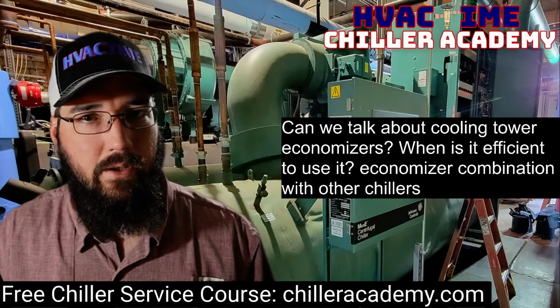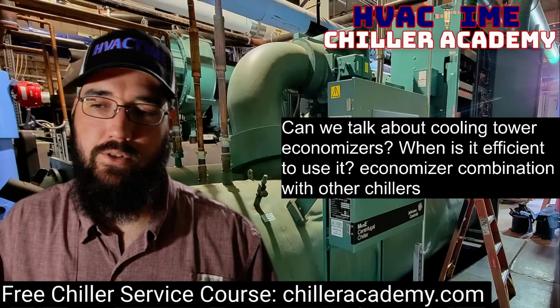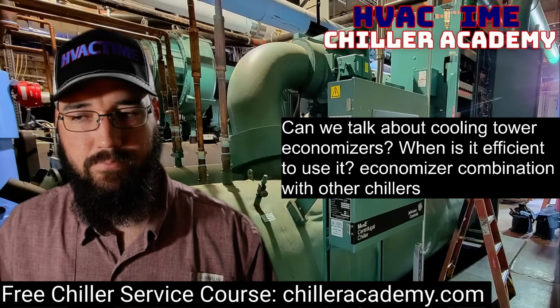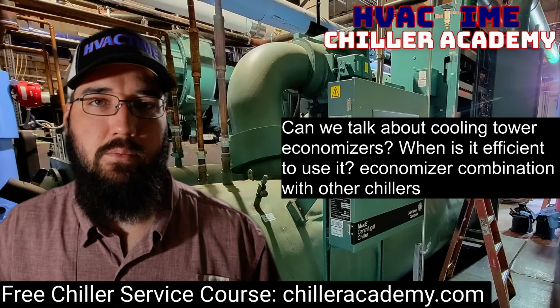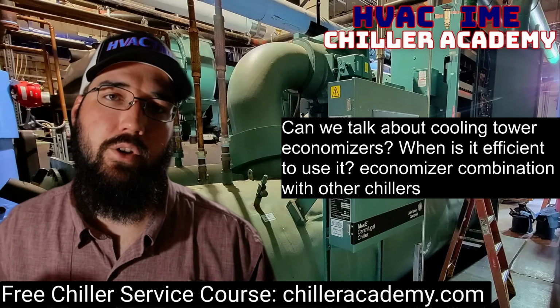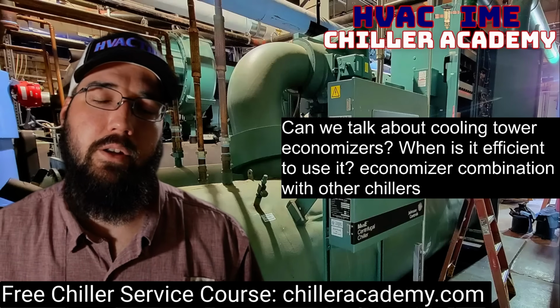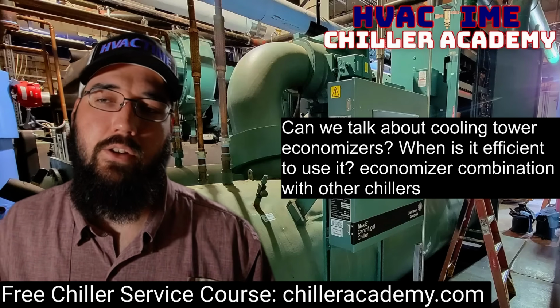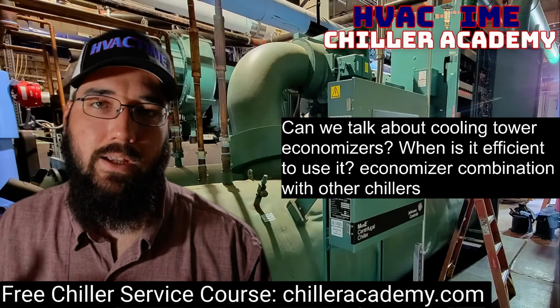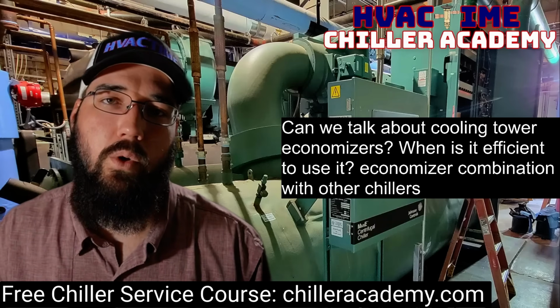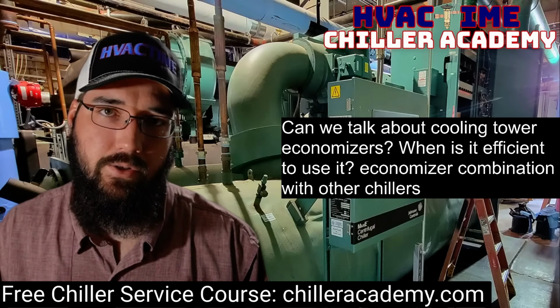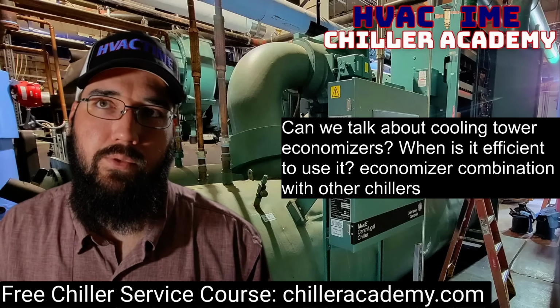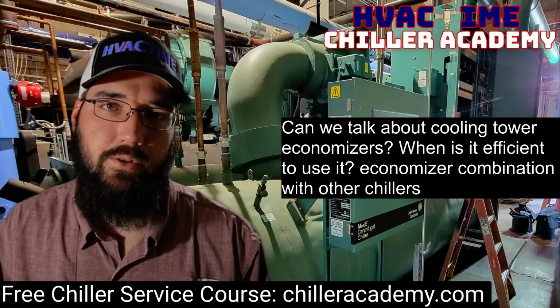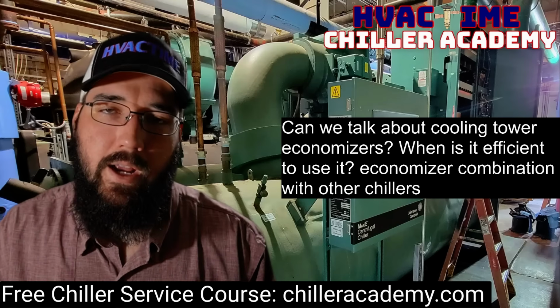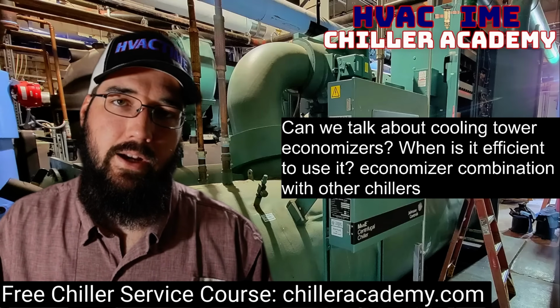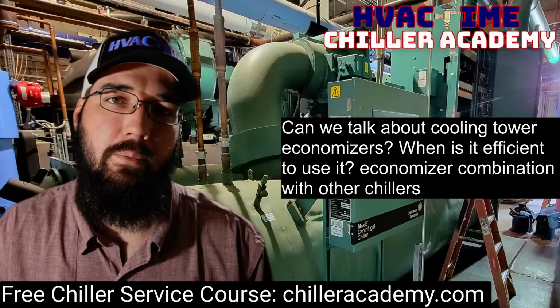If you're not expecting that, or you've got chillers that can just take that on the fly and it's no big deal, then you've got a lot more flexibility. But if you've got a situation where you know that you're only going to be in part load part of the day, and you're going to need to stage on the mechanical later in that day, well, you probably don't want to go into economize in that situation, especially if the team on site monitoring those chillers are not trained on what to do if the chiller has a hard time overcoming an inversion.